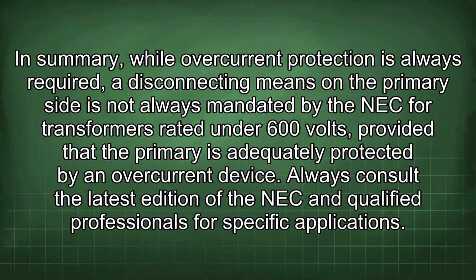In summary, while overcurrent protection is always required, a disconnecting means on the primary side is not always mandated by the NEC for transformers rated under 600 volts, provided that the primary is adequately protected by an overcurrent device. Always consult the latest edition of the NEC and qualified professionals for specific applications.